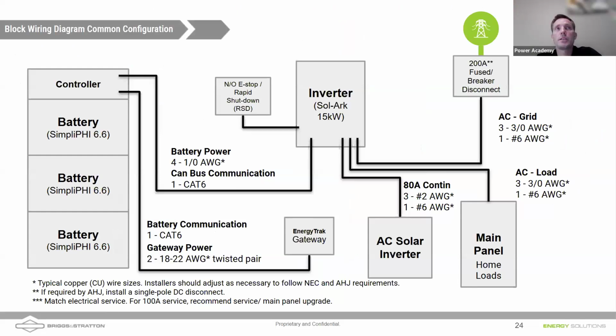Yes, you cannot. The SolarEdge inverters are not grid forming inverters. They do not have the ability to DC couple to a battery. We cannot connect our batteries directly to a SolarEdge inverter. And in fact, all these SolarEdge inverters that you see out there on houses are not grid forming. They do not have the ability to provide backup from a battery.